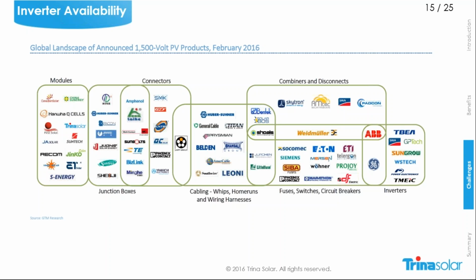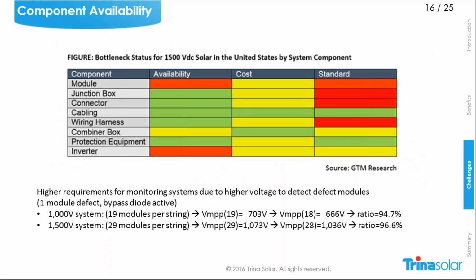Due to the limited availability, there's also the scaling effect. So it can also be expected that in the future, with the scaling, the cost of combiner boxes and inverters will also drop, and be similar to a 1000 volt system. If you now take a look at another picture from GTM, Green Tech Media, here you can see the availability. Modules are marked here in red, I would say it's more in the direction of green, because we have already installed a lot of, for example, glass modules around the world. For inverters, I would say yes, depending on the inverter you're looking for. For central inverters, it's better than for string inverters.